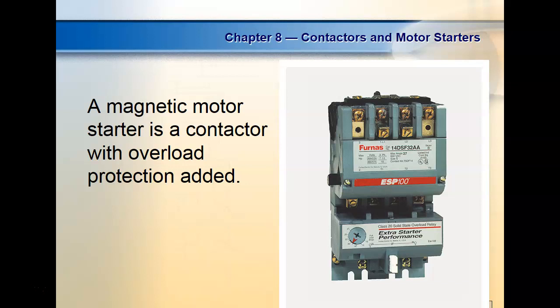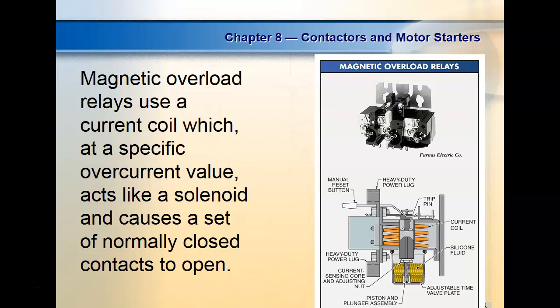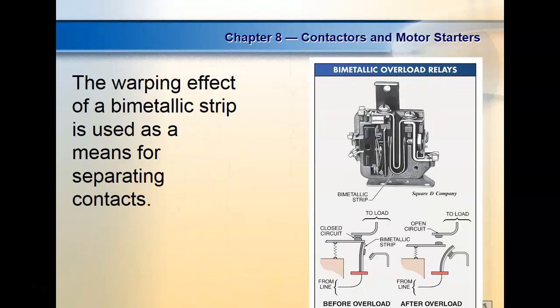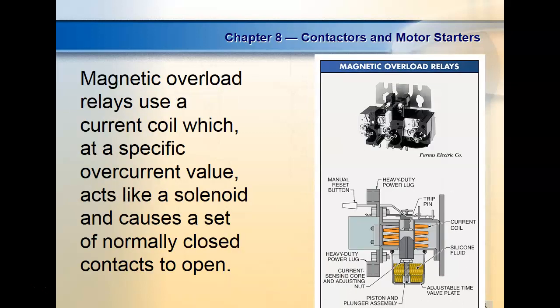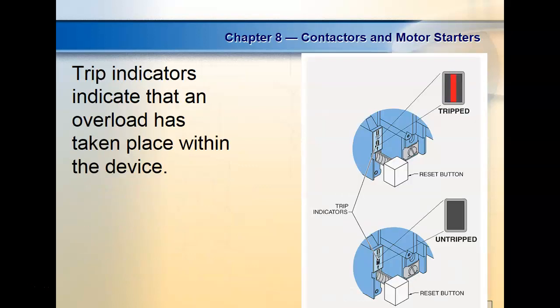If we come over to this little one right here, you notice the overload is sold as a contactor with an overload. We've got one over there on the Amco line where they've mounted the overloads to the side. These are bimetallic strips. We have magnetic overloads and bimetallic strips with a trip indicator. Just about all these overloads have a trip indicator on them.